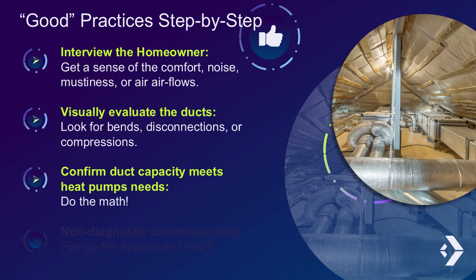Once you've completed the visual inspection, do the math on any sections that look tight, have lots of bends, or are known to have comfort issues with the existing furnace. Compare duct trunk and branch capacities to your airflow requirements from Manual S. Use National Comfort Institute standardized duct sizing tables to guide your calculations.